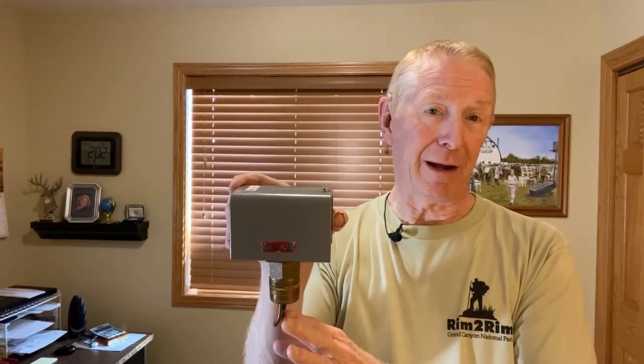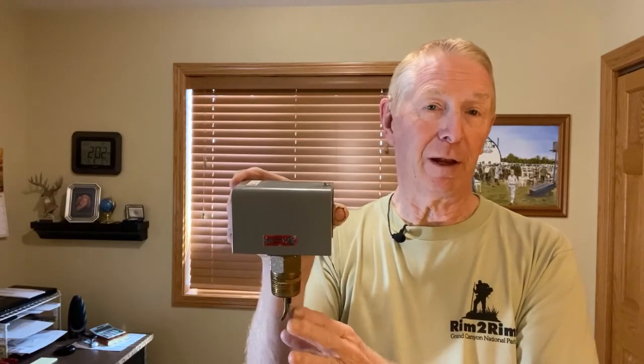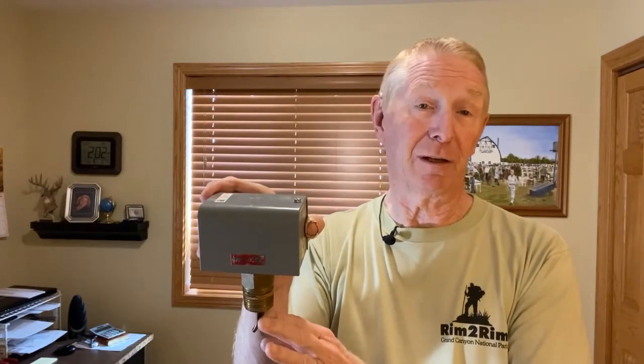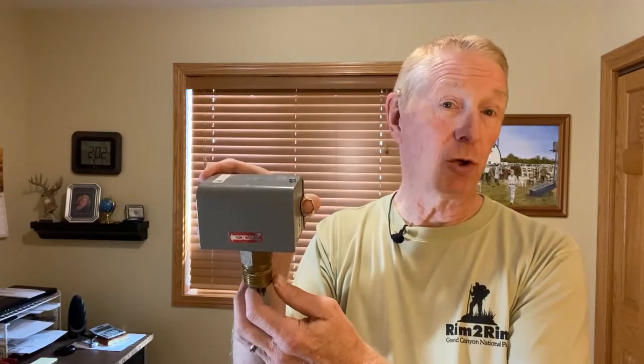These are generally installed with a directional arrow on them. And I can tell you from personal experience that these can go bad. Sometimes they are problematic. Sometimes it takes quite a few years for that to happen, of course. But when they fail, they usually fail in the off position. So your boiler won't start if these go bad in most cases.